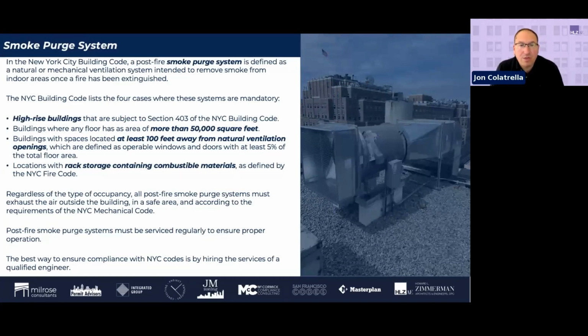So really, one thing very important to talk about is this is a post-fire smoke purge system. This system is not designed in any way to help fight the fire, but more to evacuate all of the smoke from the building after the fire has been extinguished. So it really gets classified a little bit differently because it's not actually actively trying to extinguish a fire, but actually resume the building to normal use after the fire has been extinguished by the FDNY or the automatic sprinkler system. New York City Building Code lists 4 cases where these systems are going to be mandatory.